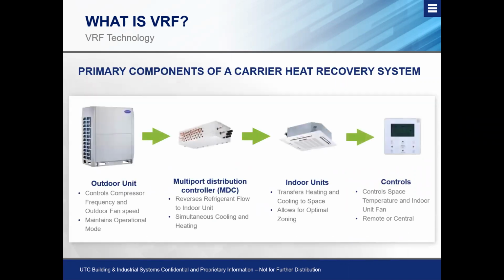Now we look at a carrier heat recovery system. You can see here we have our outdoor unit, our indoor unit, and controller. You notice the difference between the previous slide for a Toshiba carrier heat pump and a carrier heat recovery is, on the heat recovery, we have what we call on this system an MDC, which is a multi-port distribution controller. Essentially, this box is what allows us to simultaneously heat and cool and allow each individual zone to have a call for heat and a call for cool, and be able to recover that heat or recover the cooling throughout those zones and distribute it on an as-needed basis to take care of multiple spaces without a mode conflict between a heating and a cooling call.